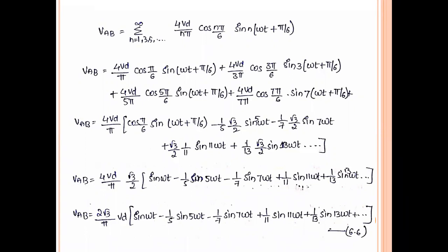Next, the harmonic content in the motor current increases at low speeds because of these low order harmonics, which means the motor has a chance to operate under saturation for light loads. That is because of a high V by F ratio.